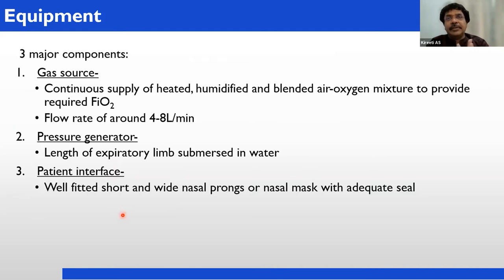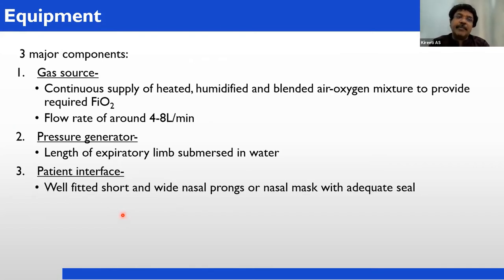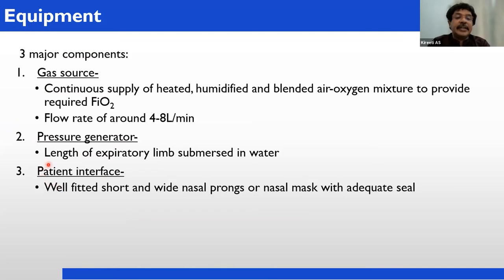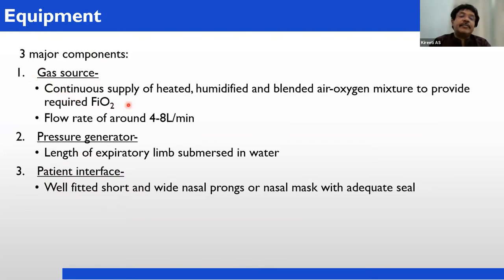Coming to equipment: CPAP has three major components. One is the gas source — from the oxygen source to the blender, providing a continuous supply of heated, humidified, blended air-oxygen mixture. From central oxygen or oxygen cylinder, oxygen will come; the blender collects air, mixes it with oxygen, and sends the blended air-oxygen mixture to the humidification chamber.